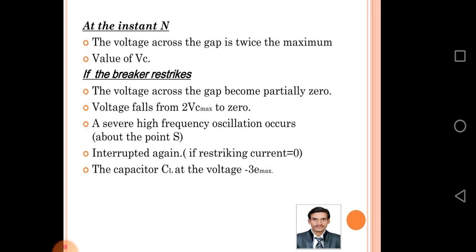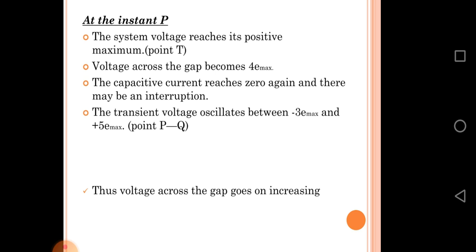The oscillation occurs about point S and the current is interrupted again when restriking current is zero. The capacitor Cl is at voltage negative 3 E max. At instant P, the system voltage reaches its positive maximum. At point T, voltage across the gap becomes 4 times E max. The capacitive current reaches zero again and there may be an interruption. The transient voltage oscillates between negative 3 E max and positive 5 E max.